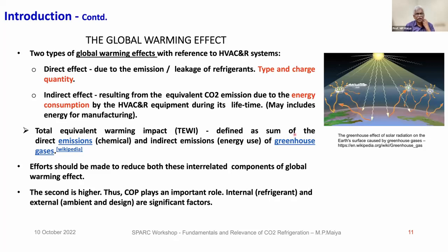So this gives a TEWI effect. The refrigerant used in the system has two effects. One is, if you release it, what will happen? What is the effect? That is the direct effect. The indirect effect is over its lifetime: it uses electric power. Where will it come from? It may come from coal burning or anything. So what is the effect of that? That is indirect, by consuming power. So one has to put together the combined effect.